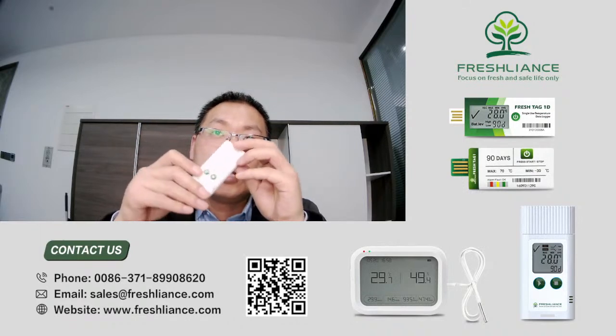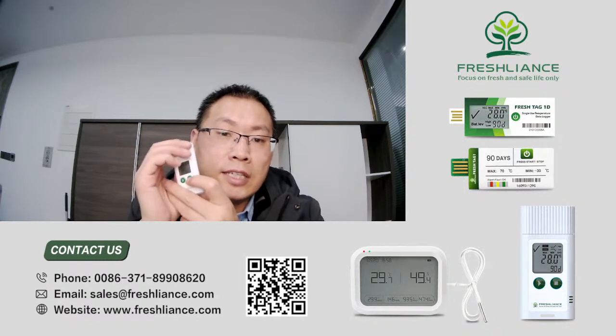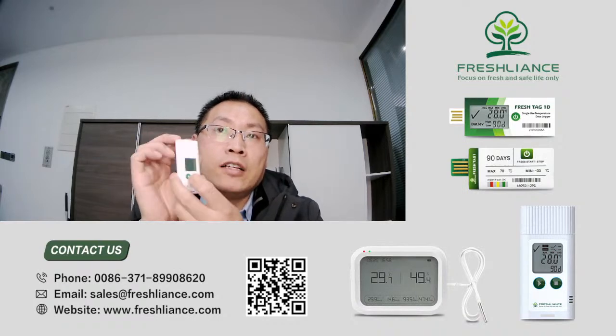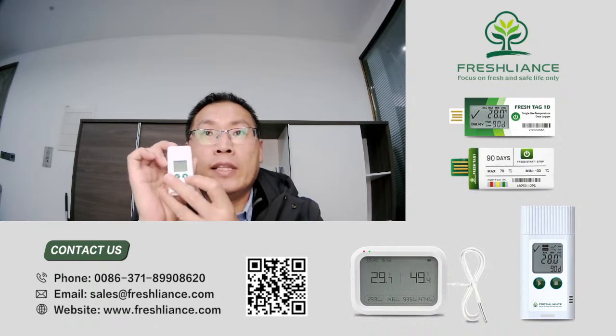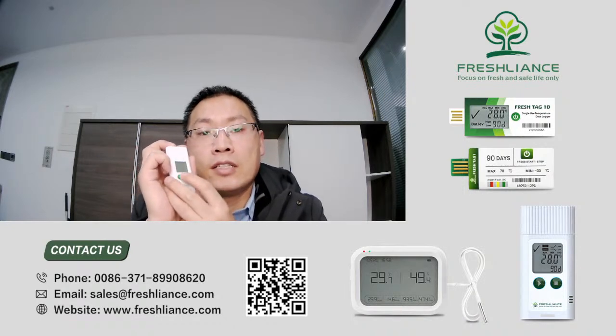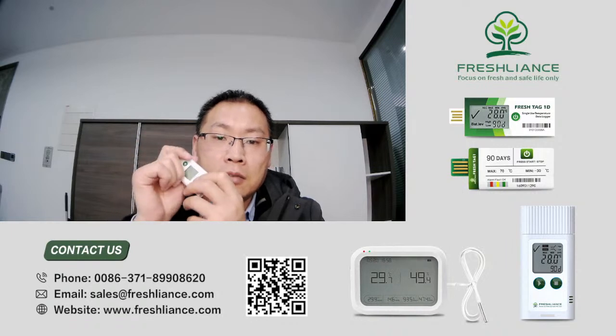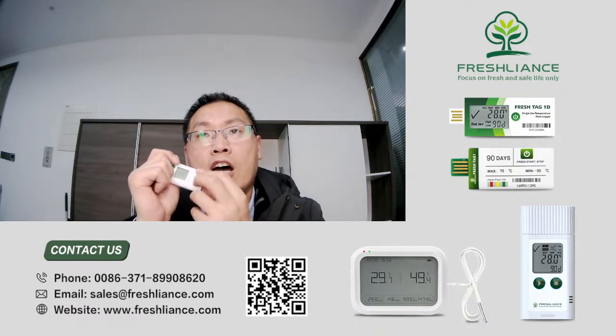This type of temperature data logger supports a temporary report, to distinguish from some single trip data loggers. You can only get the report when the recording is stopped. But for our Tech Plus T and TH temperature and humidity data loggers, it supports the temporary report. Just during the recordings, if you want to get a temporary report to check the monitoring and recording status, you can just plug the logger into the computer, and the temporary report will be generated automatically.